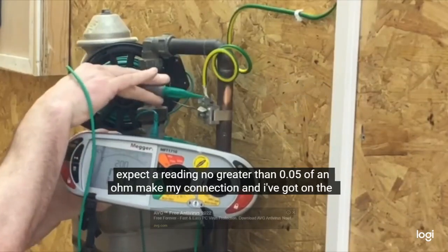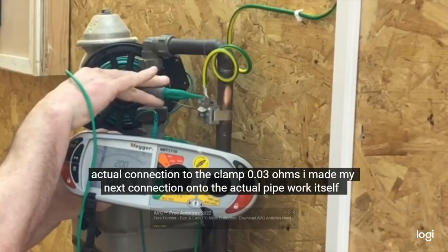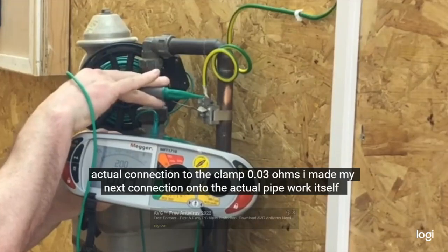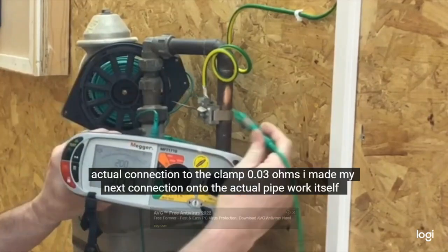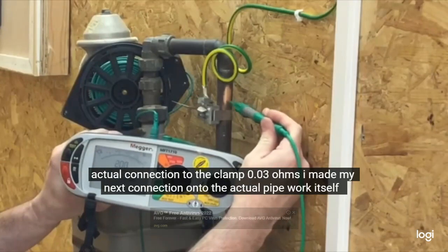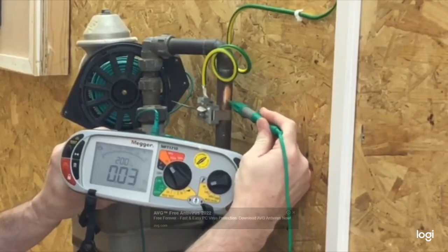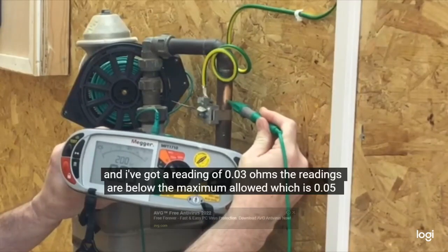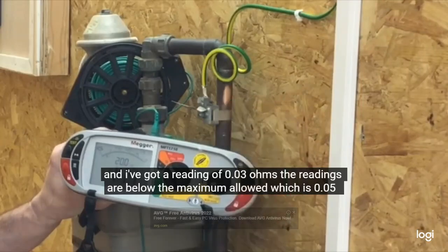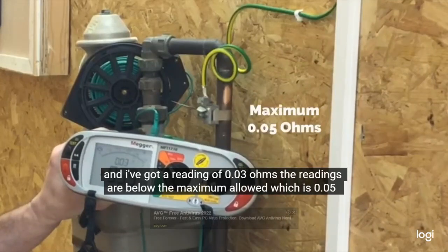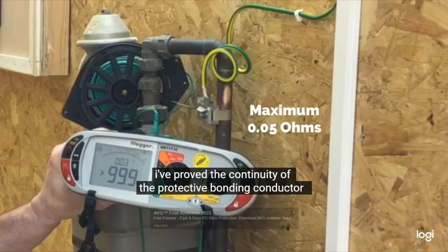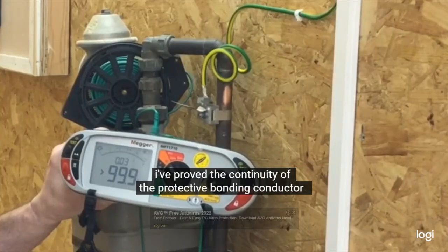I make my connection, and on the actual connection to the clamp I've got 0.03 ohms. I make my next connection onto the actual pipe work itself, and I've got a reading of 0.03 ohms. The readings are below the maximum allowed, which is 0.05. I've proved the continuity of the protective bonding conductor.